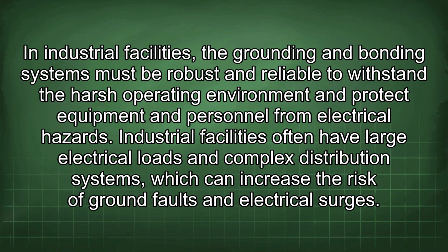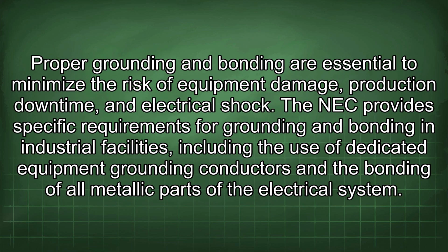In industrial facilities, the grounding and bonding systems must be robust and reliable to withstand the harsh operating environment and protect equipment and personnel from electrical hazards. Industrial facilities often have large electrical loads and complex distribution systems, which can increase the risk of ground faults and electrical surges. Proper grounding and bonding are essential to minimize the risk of equipment damage, production downtime, and electrical shock. The NEC provides specific requirements for grounding and bonding in industrial facilities, including the use of dedicated equipment grounding conductors and the bonding of all metallic parts of the electrical system.